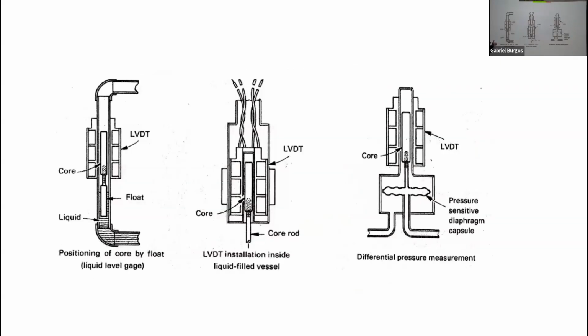Let's see, here's what I was looking for. Here's some examples of LVDTs hooked up. This one has a diaphragm, so you can measure low pressures with it. It's a common way of making low pressure sensors, before the days of silicon-based units that are now capable of doing the same thing. Here's one where essentially this is a blanked-off bore, so it can be subjected to fluid, as long as it's not a magnetic fluid, which is rare. You can use this to put into various other mechanisms, like inside of a valve, for example.